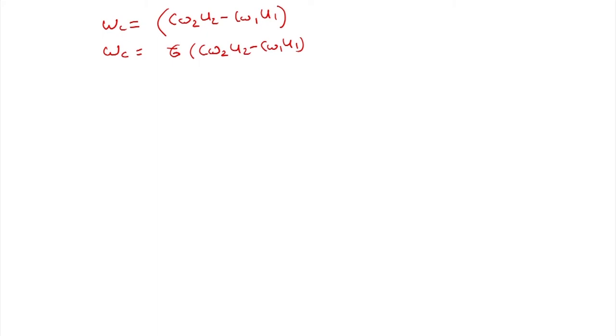We had seen that the work input for the compressor was Cw2 U2 minus Cw1 U1. This was an ideal work input required to give the desired pressure rise. Here we have also seen that due to the slip factor, this work input gets altered and we get the formula Cw2 U2 minus Cw1 U1 into sigma. This slip factor was mainly due to the inertia of the air to follow the tangential velocity at the impeller section. Further, this work input would get altered due to the friction, also called windage.